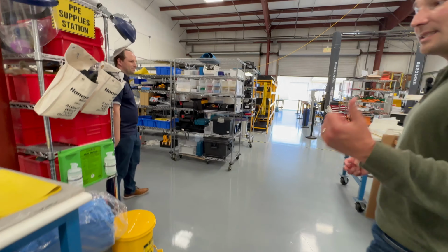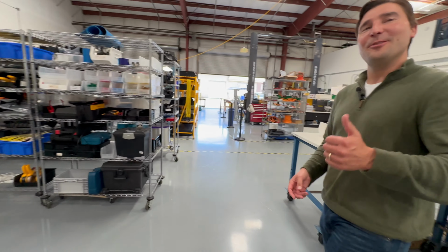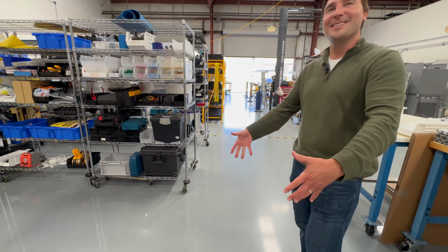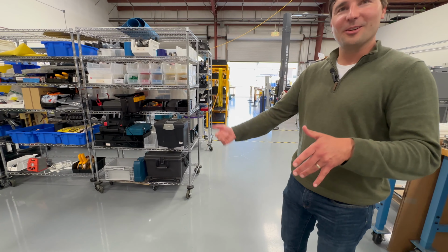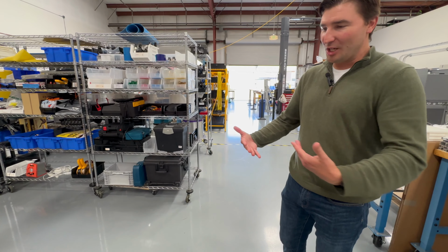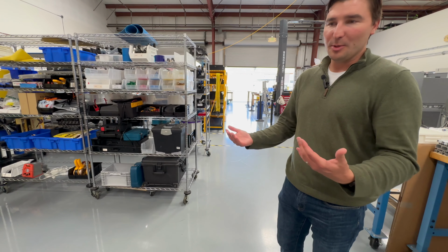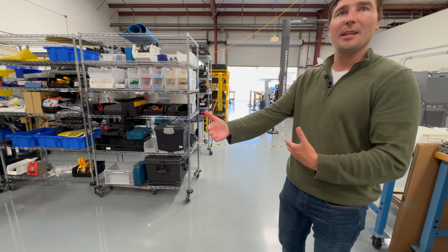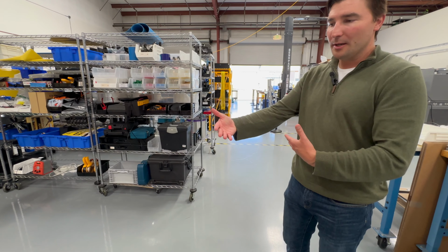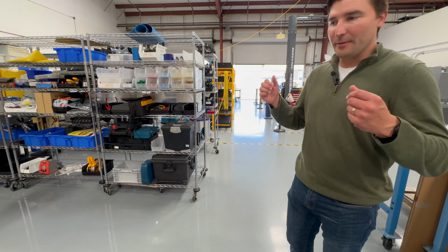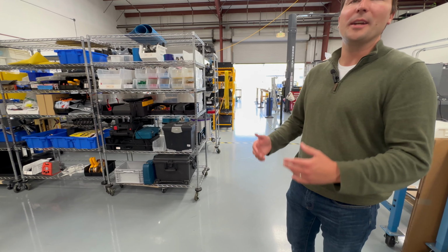One thing that's actually really nice about the marine environment is you have an infinite thermal reservoir with the water. So basically, you can have a heat exchanger with either lake or seawater that then exchanges it with a coolant such that you get between 15 degrees C and 30 degrees C water, and then you can basically evacuate as much heat as you want out of that.